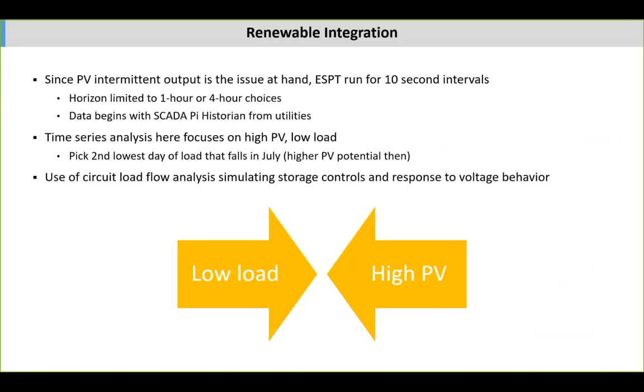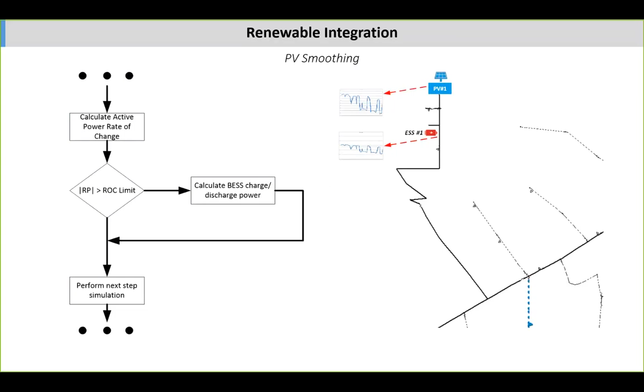Here's an example showing a circuit with a battery. It looks at the rate of change of the PV power and says if it gets outside a rate of change limit, use the battery to charge or discharge and mitigate the amount of injection the PV is putting into the system. So PV smoothing doesn't require big batteries, but it requires local, fast, autonomous control, because you're just trying to mitigate the rate of change of the voltage.